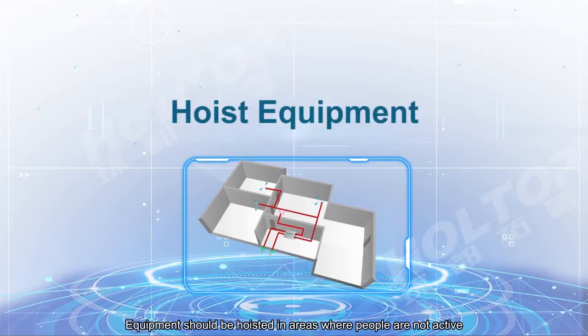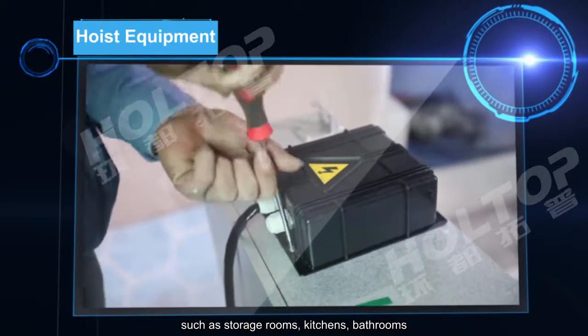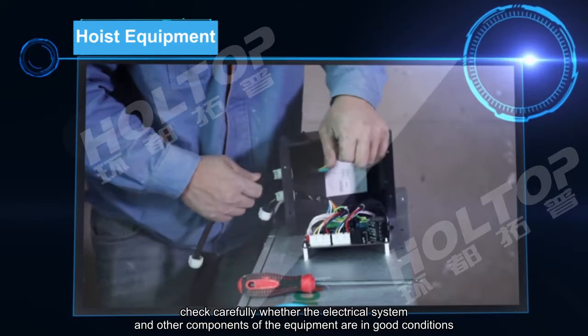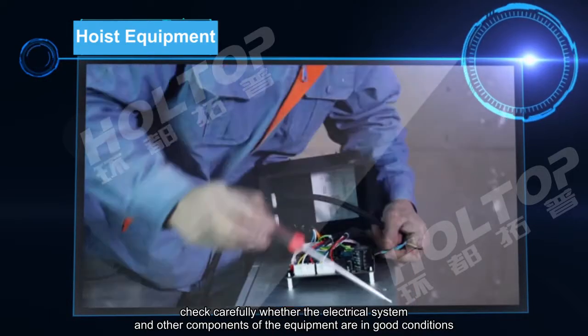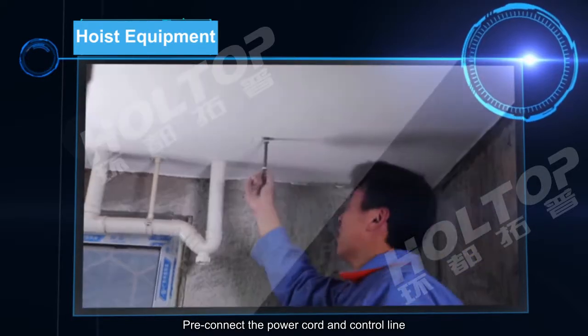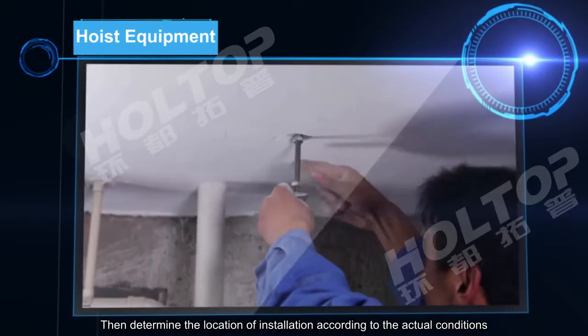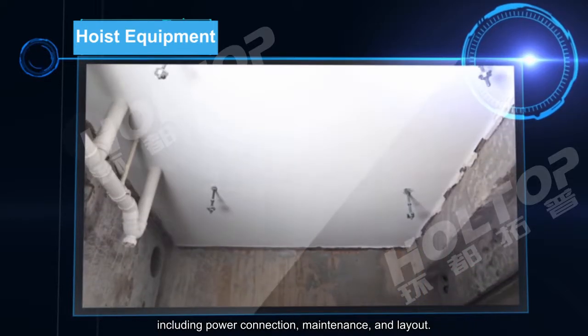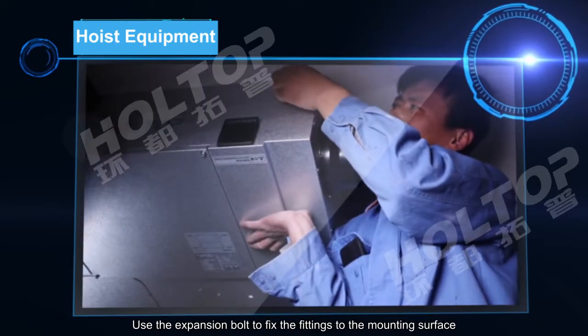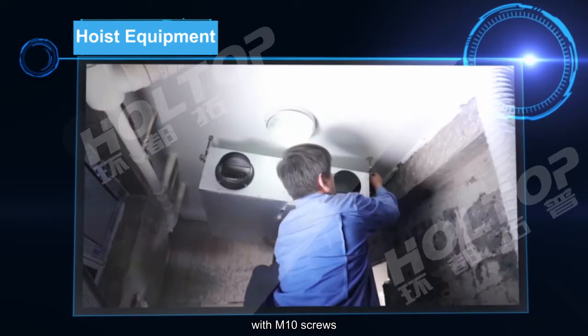Equipment should be hoisted in areas where people are not active, such as the storage room, kitchen, or bathrooms. Before installing the equipment, carefully check whether the electrical system and other components are in good condition. Preconnect the power cord and control line, then determine the installation location according to actual conditions, including power connection, maintenance, and layout. Use expansion bolts to fix the fittings to the mounting surface with M10 screws.